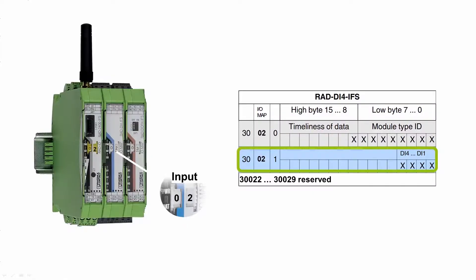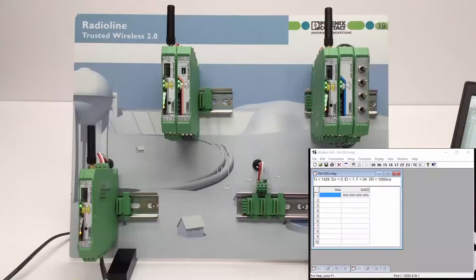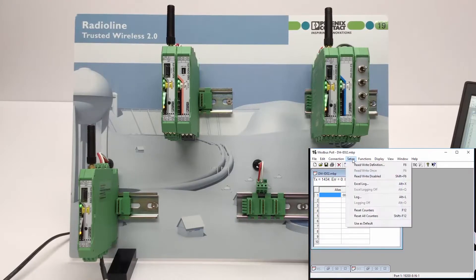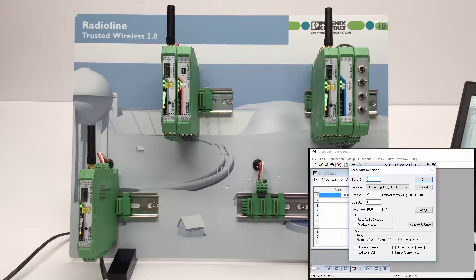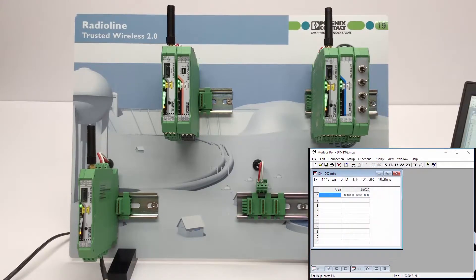If the white thumb wheel of an input module is set to I/O map address 02, the process data is stored in the register with address 30021. To address an input module, Modbus function code 04 is used to read the register. Please note that the Modbus protocol differentiates between register number (1-based) and register address (0-based). Depending on the method used, the register address may differ by 1.